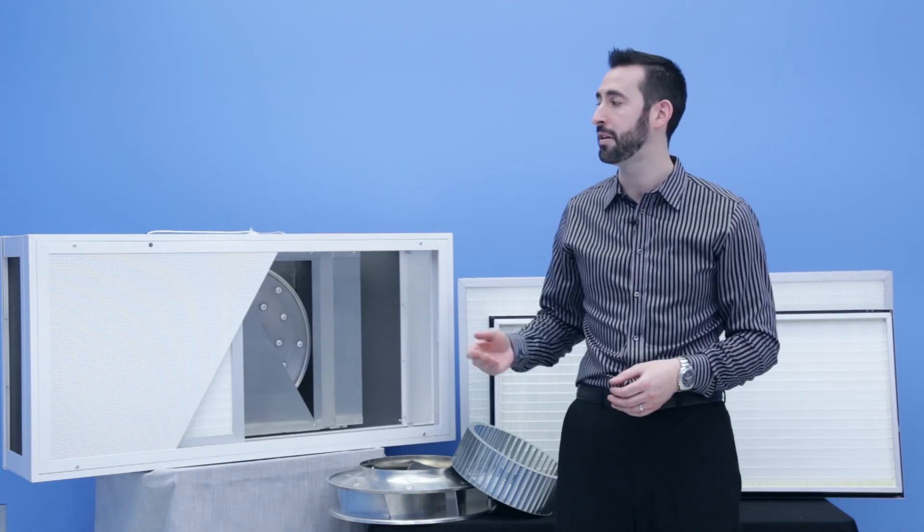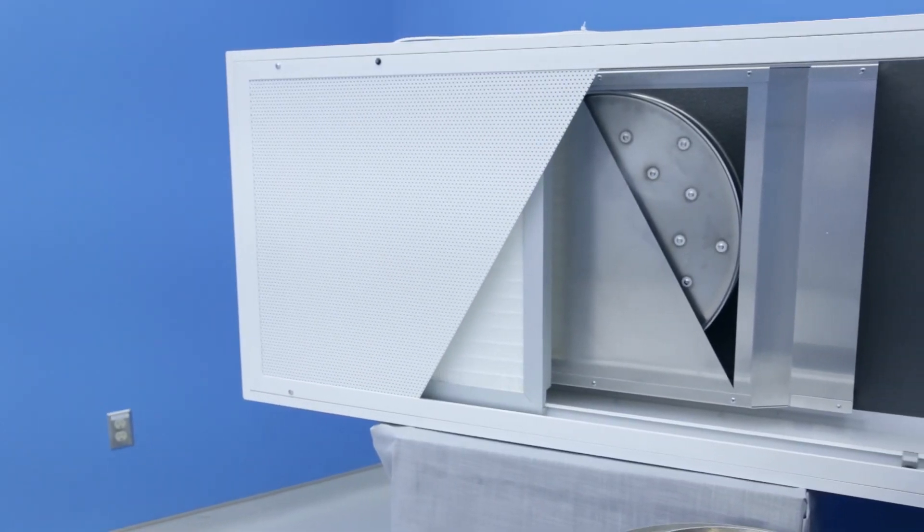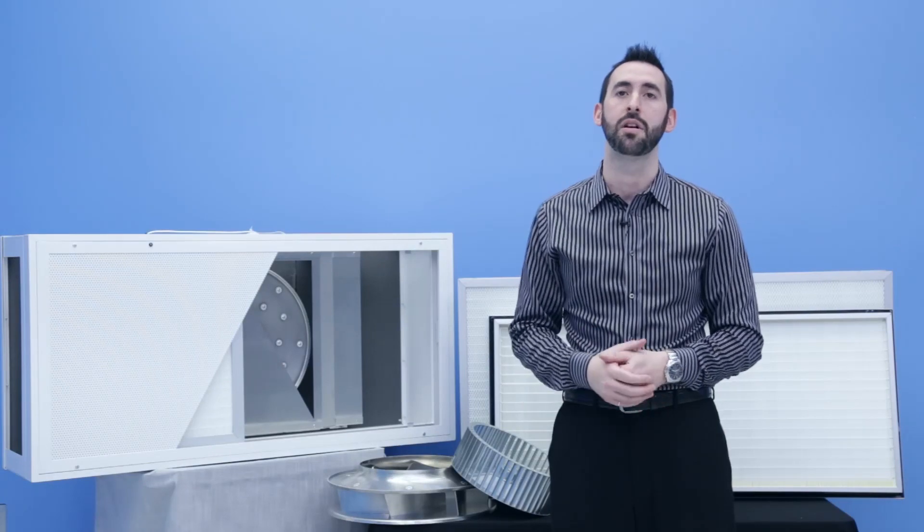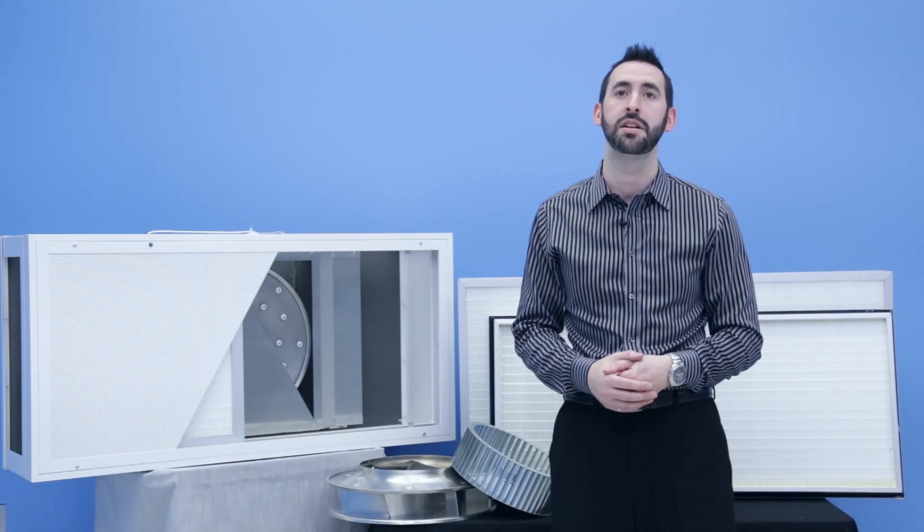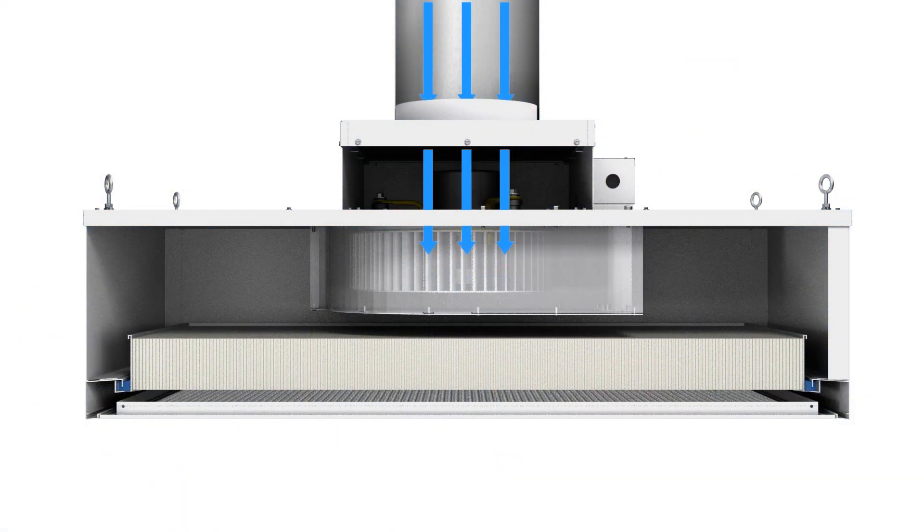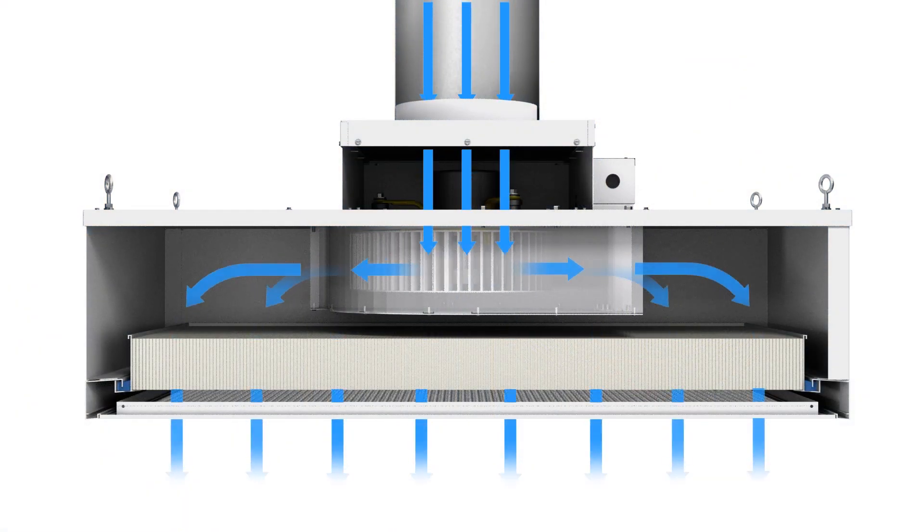A fan filter unit, or FFU, is essentially a laminar flow diffuser with an integrated fan and motor. The fan and motor are there to overcome the static pressure of the internally mounted HEPA or ULPA filter. This is beneficial in retrofit applications, where the existing fan power from the air handler is insufficient to overcome the filter pressure drop.